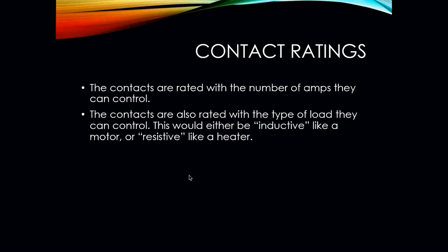The contacts are rated with the number of amps they can control. The contacts are also rated with the type of load they can control. This would be an inductive load like a motor, or it could be a resistive load like a heater. We will run into a lot of resistive heaters if we're dealing with refrigeration, for example electric heat and electric defrost. You're going to run into it in heat pumps if we're using supplemental or emergency heaters in the ductwork. That's where you will run into stuff like that. But either way, a relay is going to be used to turn that stuff on and off.